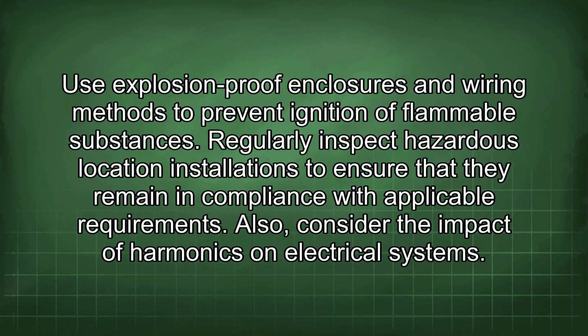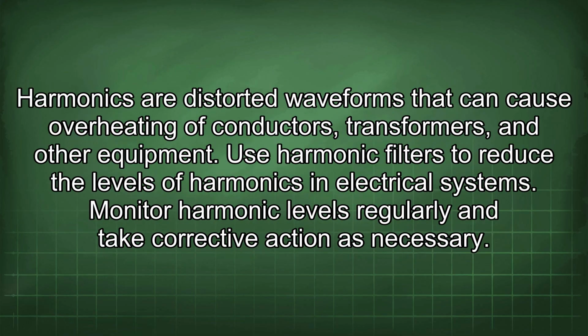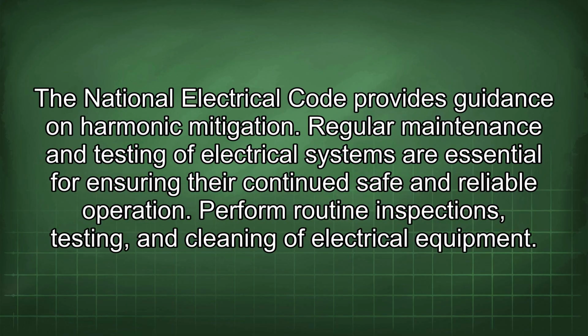Also, consider the impact of harmonics on electrical systems. Harmonics are distorted waveforms that can cause overheating of conductors, transformers, and other equipment. Use harmonic filters to reduce the levels of harmonics in electrical systems. Monitor harmonic levels regularly and take corrective action as necessary. The National Electrical Code provides guidance on harmonic mitigation.